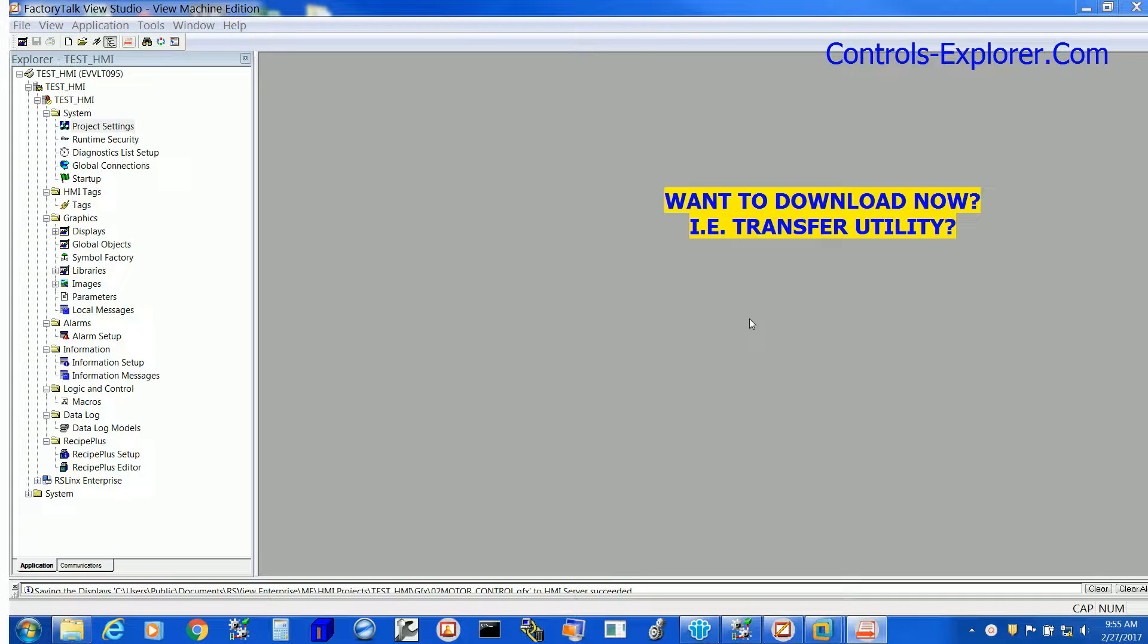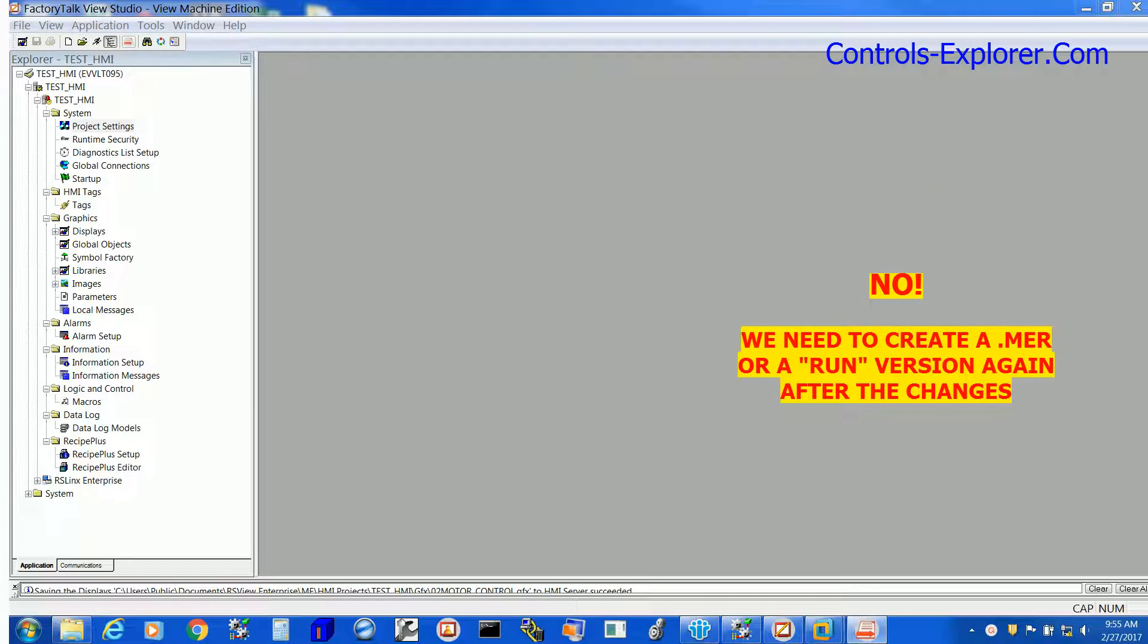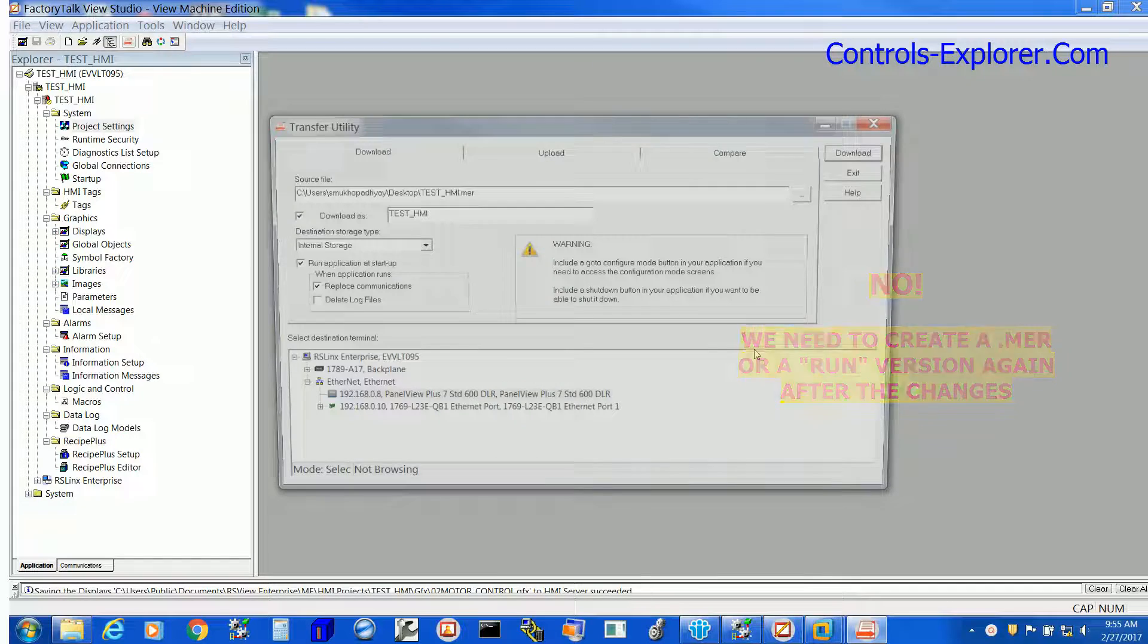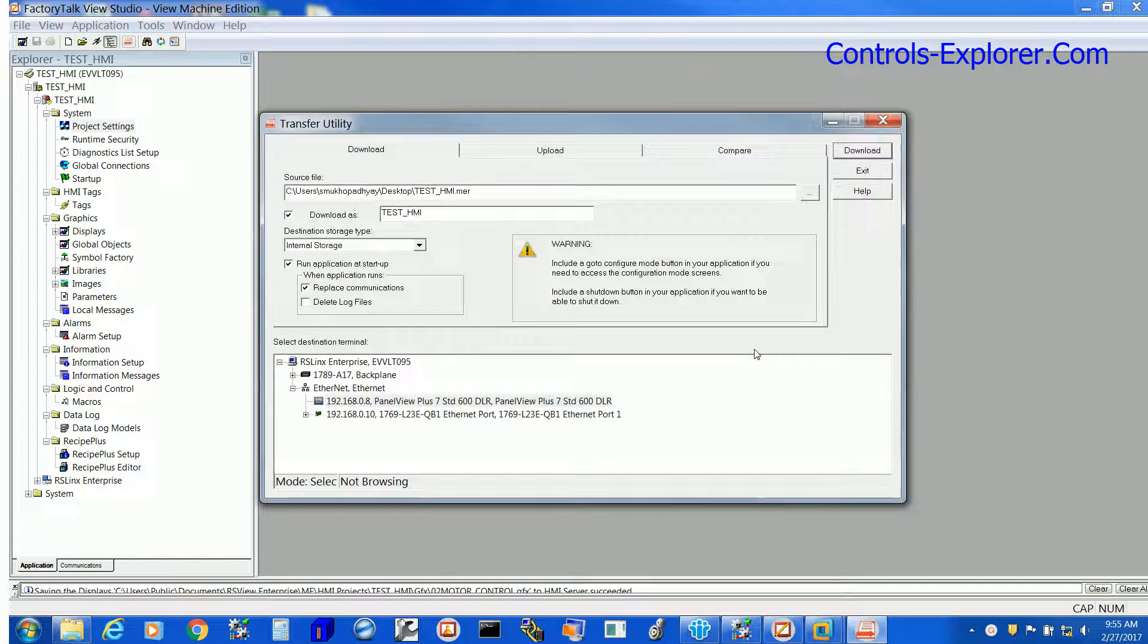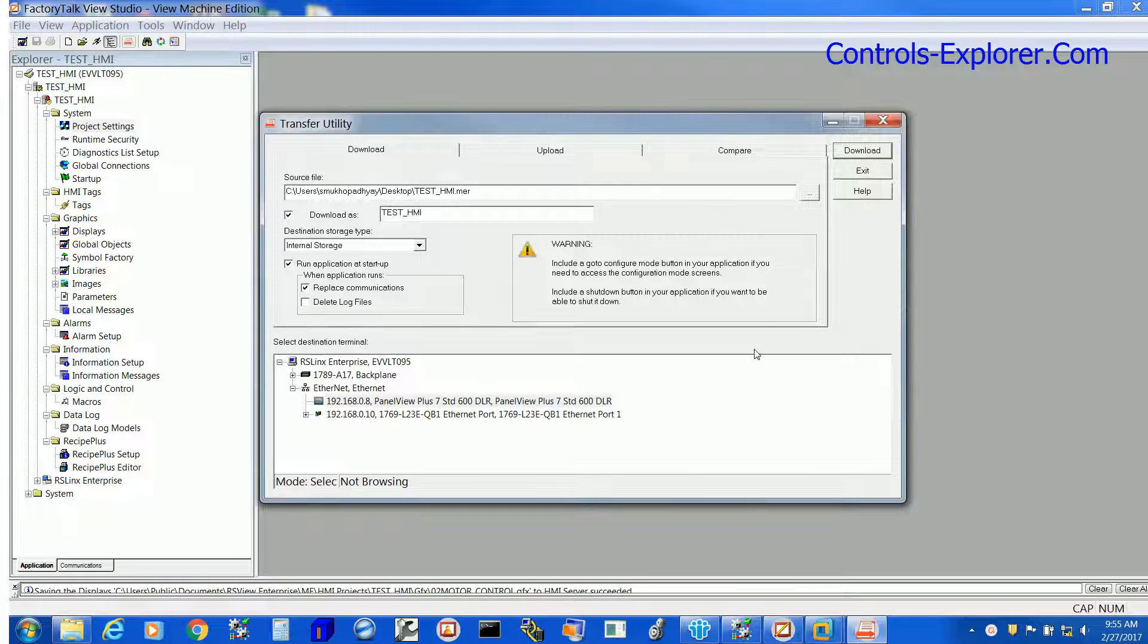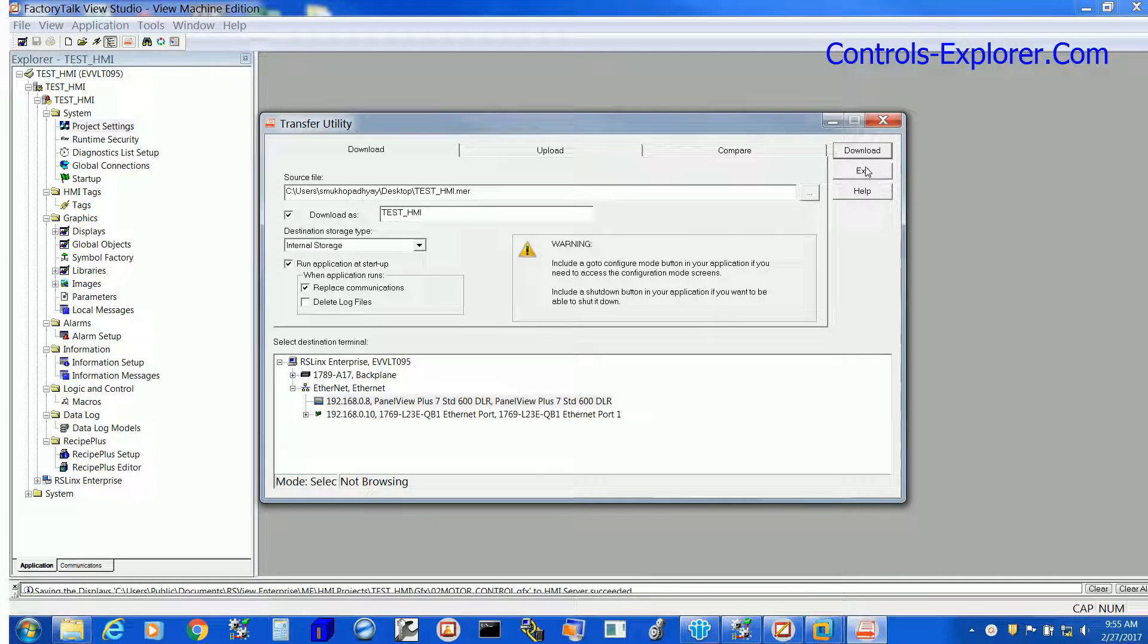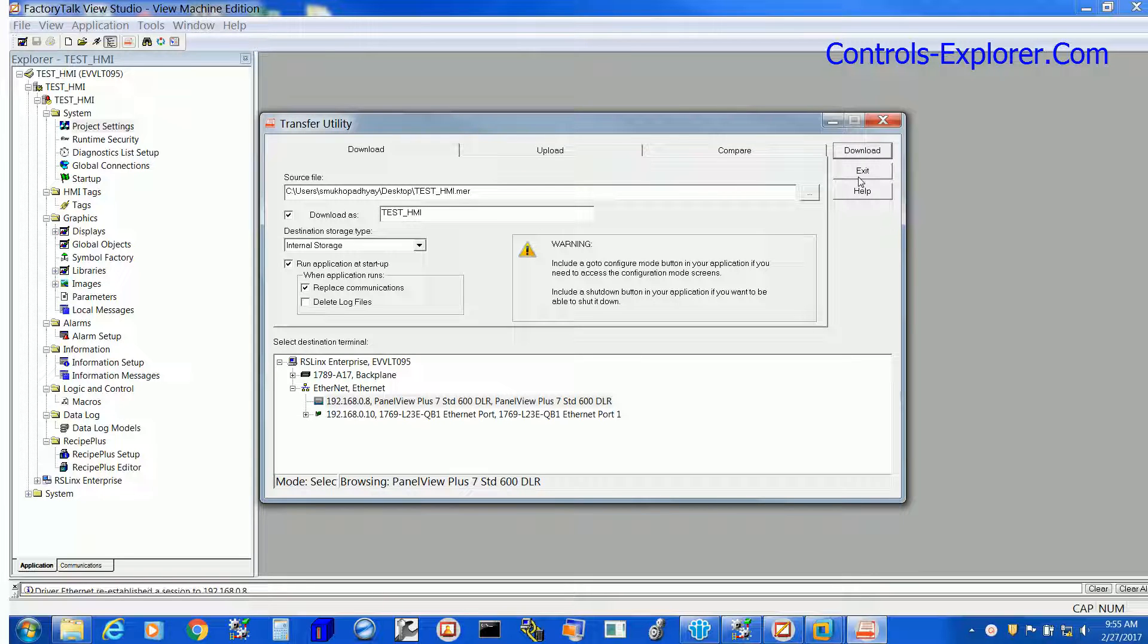Now next, we should not download the HMI program right away since every time you do a change, you have to create a new run or .mer version before you can download the HMI. So let's go back and create a new .mer version before you download those changes to take effect into the HMI.